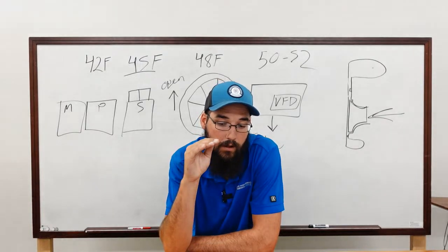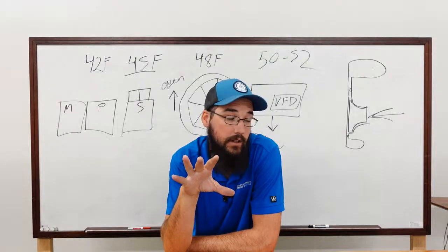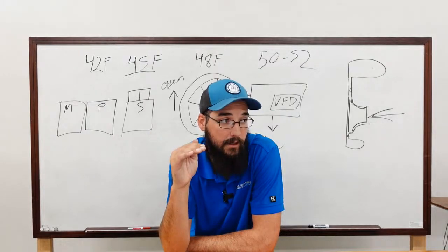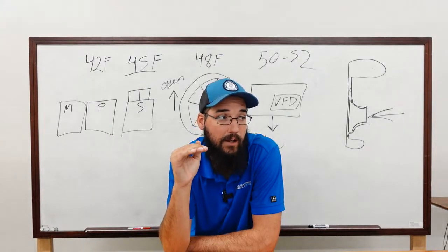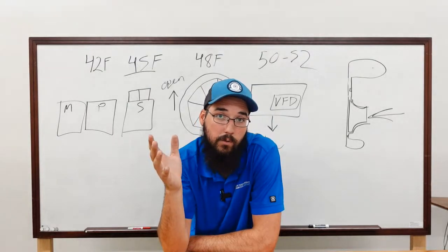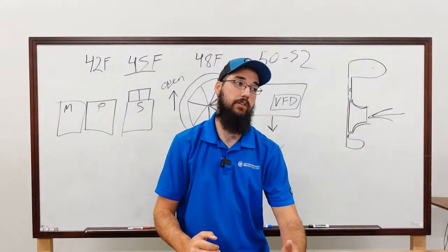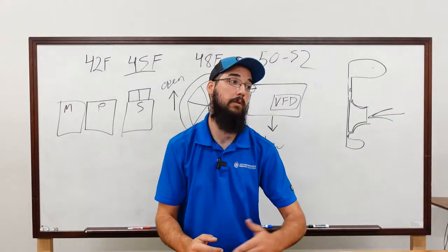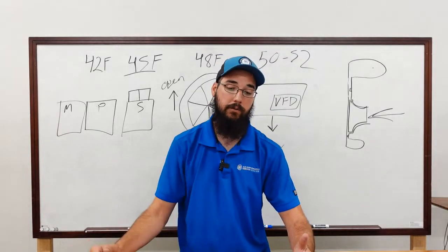So what I would do at that point, once the machine stabilizes and it's doing as much cooling as it's going to do, is bump that current limit up 5, 10% at a time and let it restabilize. Where I'm going to stop is when my condenser water begins to run outside of what I'm comfortable with for that system. If my leaving water or entering water gets above whatever condition you have, that is your breakover point. Stop raising the current limit and maybe even drop it down slightly to give yourself some buffer in case you have a little bit hotter day or a little bit more humid day tomorrow, because those things are going to affect how well that cooling tower can keep up by itself until you get the other one repaired.